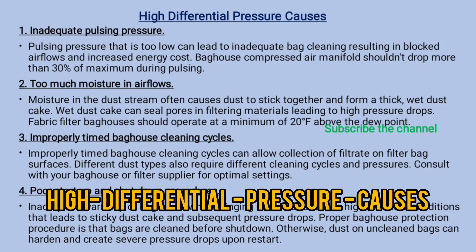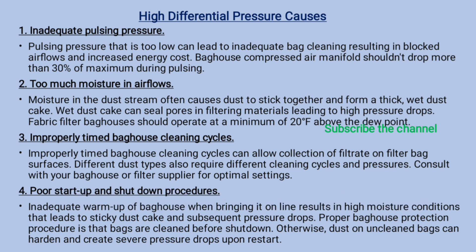Next, we understand the high differential pressure causes. Point number 1: Inadequate pulsing pressure. Pulsing pressure that is too low can lead to inadequate bag cleaning, resulting in blocked air flows and increased energy cost.